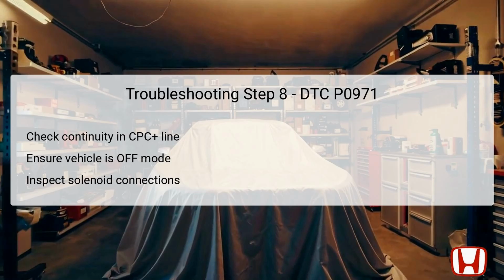A successful continuity reading indicates that further examinations may be required elsewhere in the circuitry. However, if continuity is absent, repairs must focus on the CPC Plus wire, addressing any breaks between the harness and solenoid connections to guarantee proper electrical signals for the solenoid's operational integrity.